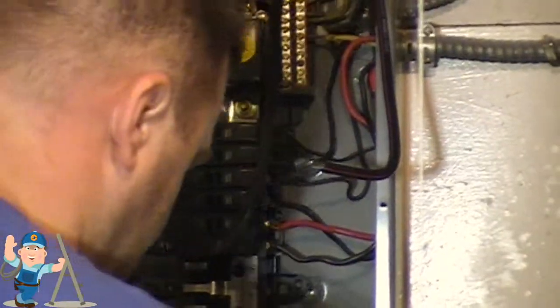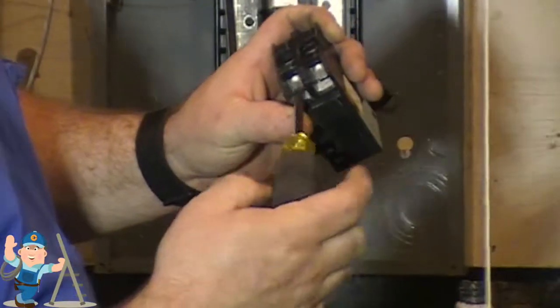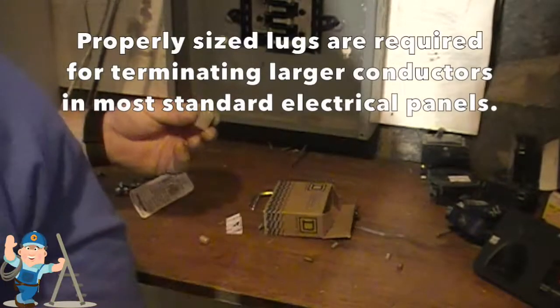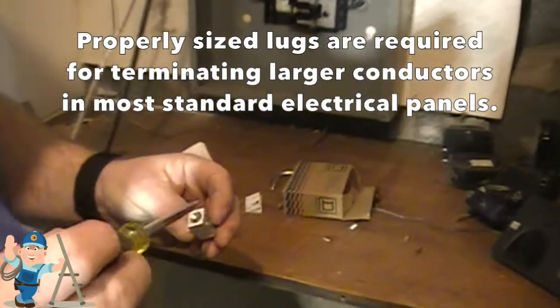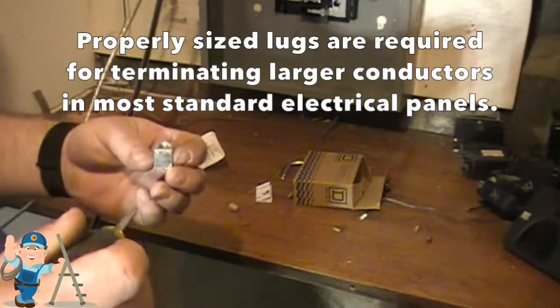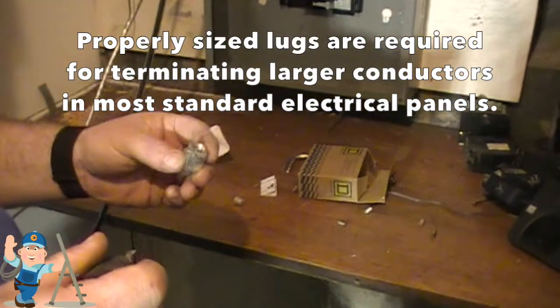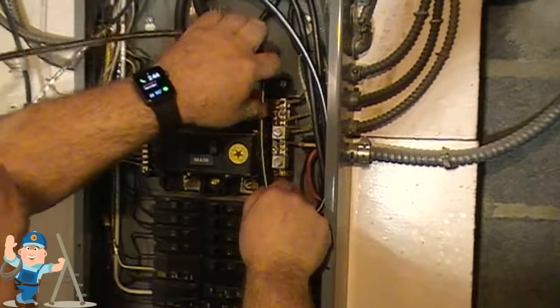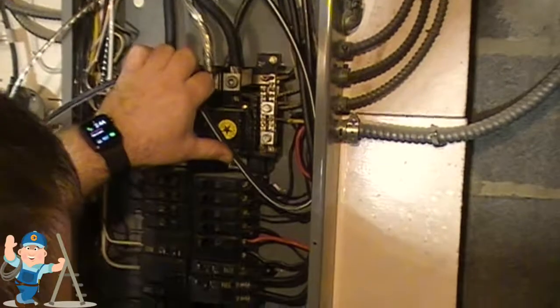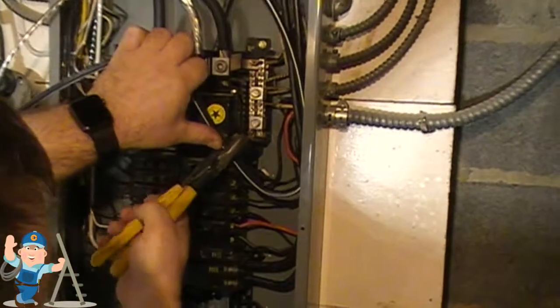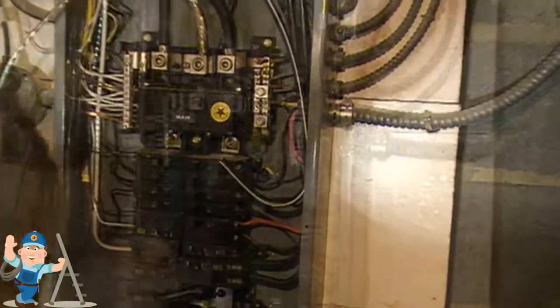What I like to do is put it on a 2-pole 90 amp circuit breaker here in the main breaker panel. The reason why I do that, I believe that's a code thing, that you can't use the 100 amp because of some derating rule in the code book. I'd have to look that up to be more specific, but this is the way I've always done a 100 amp panel with a 90 amp circuit breaker. And if you know that code section, you want to leave it in the comments, that's fine. I am a licensed electrician, and I could find it if I needed to. I know the rule, so we'll leave it at that.